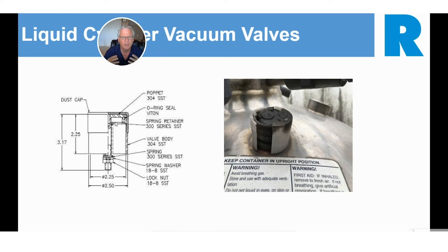You see these O-rings on these valves. If they sit out in the yard and they get hit by the ultraviolet rays of the sun and plugged with dirt, those O-rings in that valve can dry out and you can slowly lose the vacuum quality in that inner vessel of the cylinder.